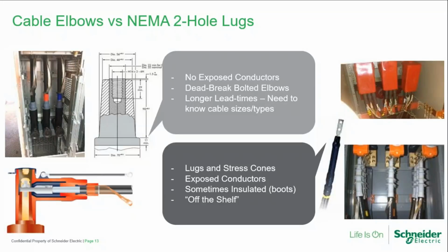The downside here is that generally these elbows have longer lead times than more common stress cones and cable lug connections. And it's important that you know the type and size of cable that you're using to make these connections, because a lot of the elbows don't have a lot of versatility in the width of cable that can be used. It's important to order the correct cable elbow for the correct size of cable that you're going to be using. And when I say size of cable, I don't just mean the size of the conductor. I mean the width of the conductor plus insulator overall on the cable. It's important to match those correctly. So while this brings a big benefit around safety and reliability, it basically just means that the ordering of the cable connections needs to move up in the timeline of the project. So it's just an important consideration.